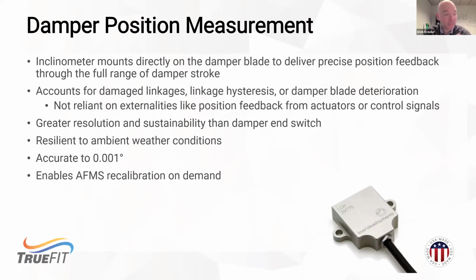The benefit of having this independent measurement is that we know where we are in that performance curve at any time, irrespective of the linkage or hysteresis that would be caused by the linkage or the damper actuator. We've removed all of those inaccuracies from the equation.